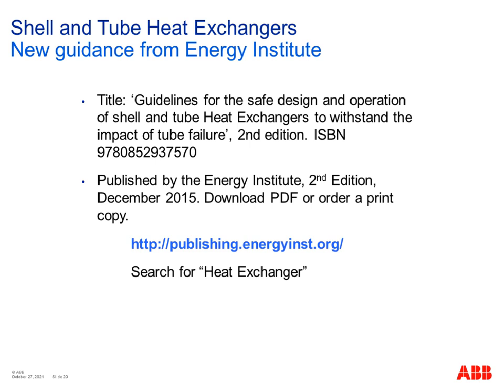So you always need to think about, okay, I do want to have this bursting disc so it can react quickly to an overpressure event, but what's going to happen if it spuriously fails, or what's going to happen if this relief event does actually occur and the rupture disc actually does rupture? What happens next? So the guidance I talked about previously is the details are given on this slide.